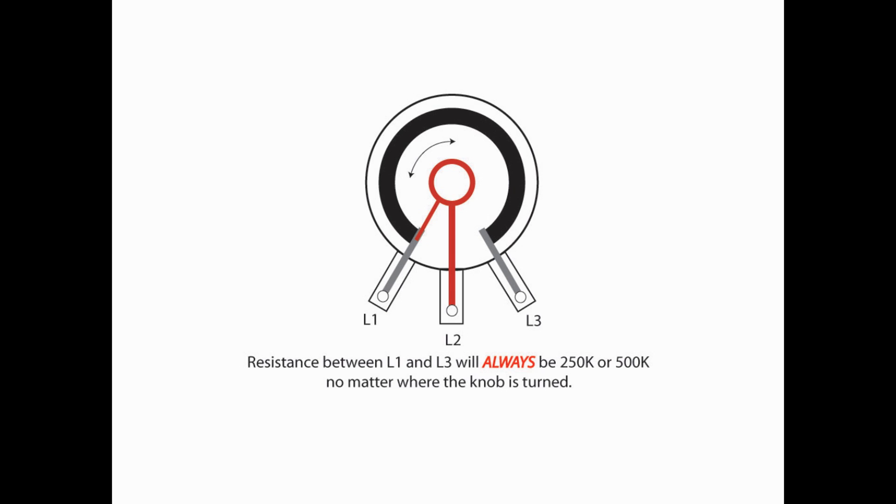Now, it doesn't matter what you do with the knob in terms of turning it to the left or turning it to the right, the resistance between L1 and L3 is constant. It will never change. What does change is the resistance between L1 and L2, or L2 and L3, and that's what I'm going to show you next.